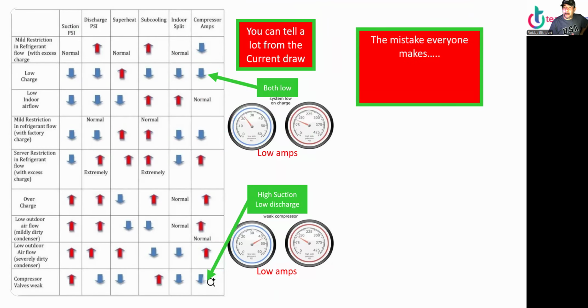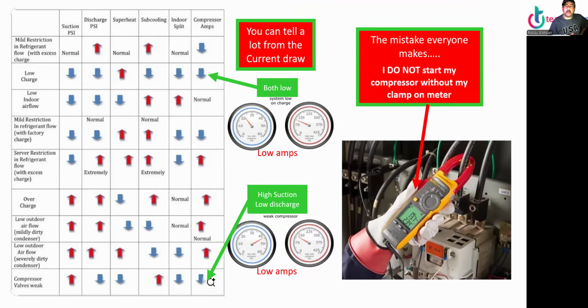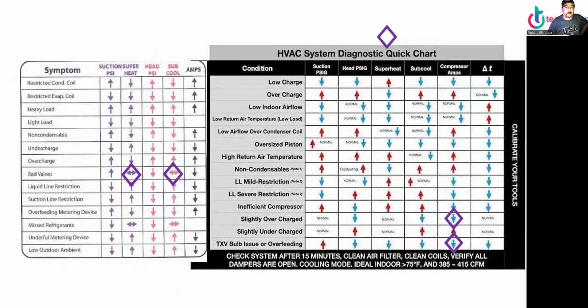The mistake everybody makes: I do not start my compressor without my clamp-on meter, people. On Facebook, all the time, people take pictures of a gauge: what's wrong with the system? And nobody tells me the amp draw. You've got to know the amp draw every time you turn on the compressor. You can tell a lot.